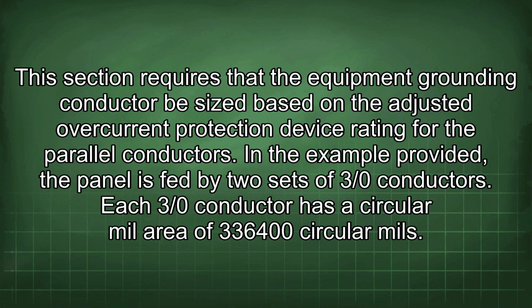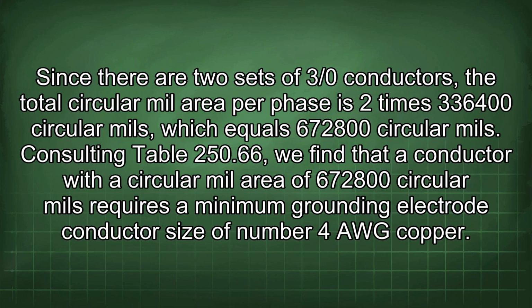Each 3/0 conductor has a circular mil area of 336,400 circular mils. Since there are two sets of 3/0 conductors, the total circular mil area per phase is 2 times 336,400 circular mils, which equals 672,800 circular mils.